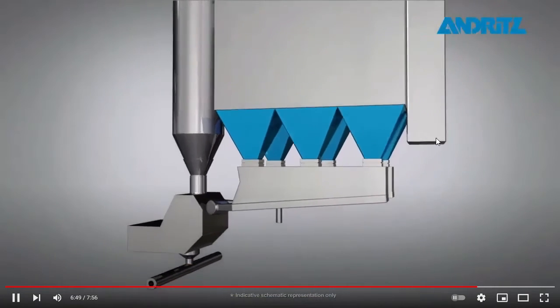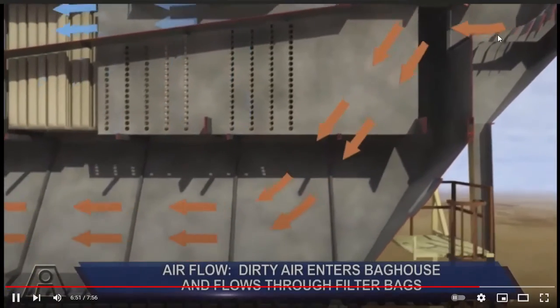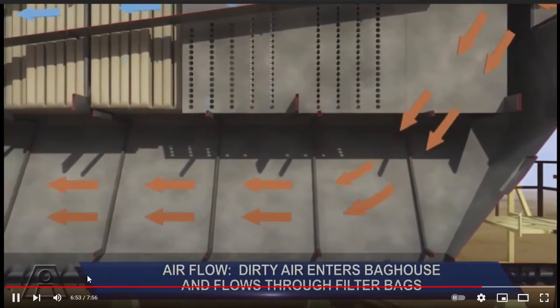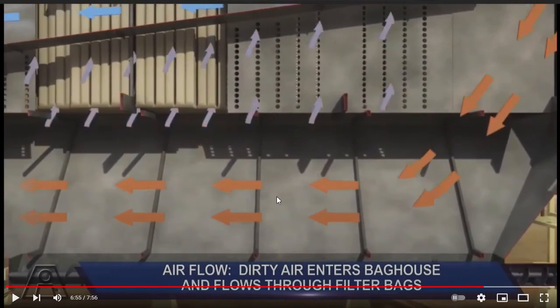But here's a better video of how the bag house works. So if you remember, you've got air with fly ash in it here. You've got those bags sitting down. The air continues through the bags, but the ash is sitting on top of the bags, and then they pulse it, and that ash falls down into the bottom, and then it goes to a silo, right?